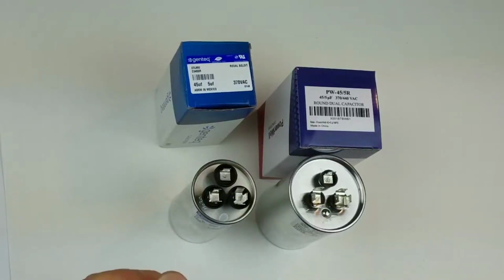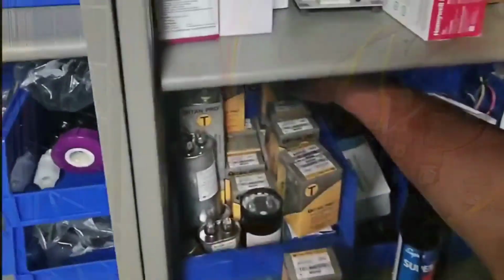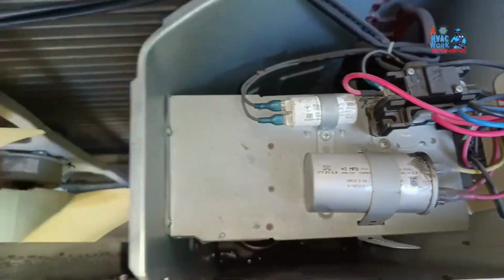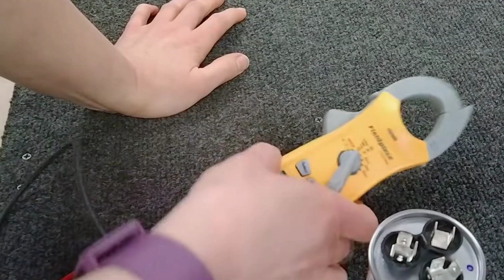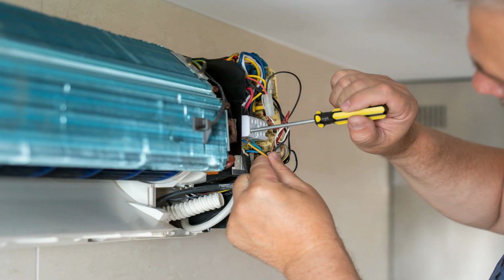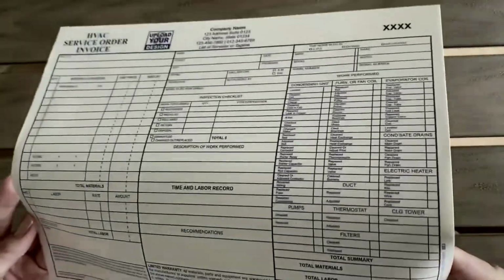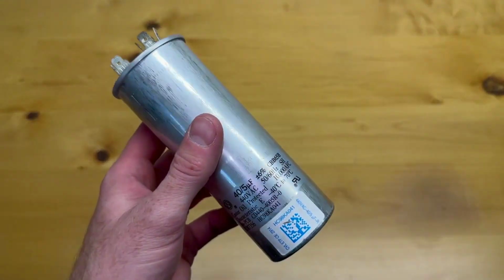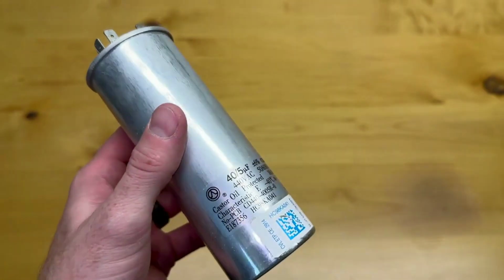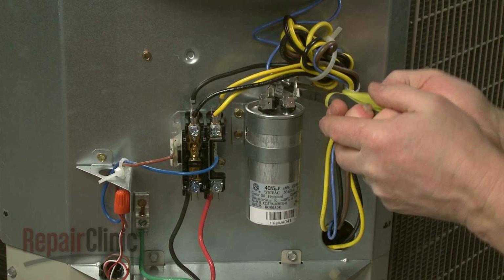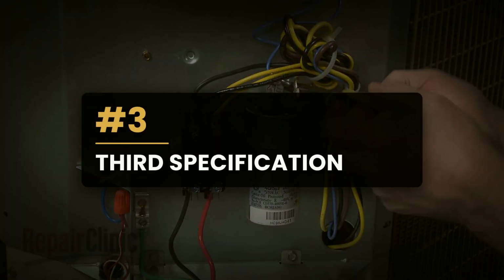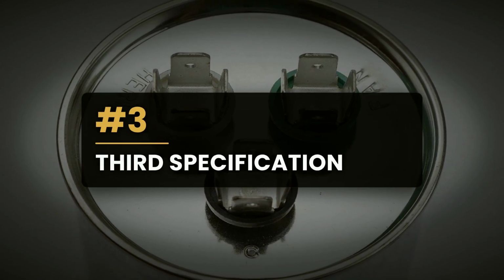The second number is the voltage rating, measured in VAC. The two most common ratings are 370 VAC and 440 VAC. Here is the rule that matters. You can install a higher voltage rating than the original. A 440-volt capacitor in a system that originally used a 370-volt unit is perfectly acceptable and provides a small margin of safety. What you cannot do is install a lower voltage rating. A 370-volt capacitor in a 440-volt application will fail quickly and potentially damage connected components. Go up, never down.